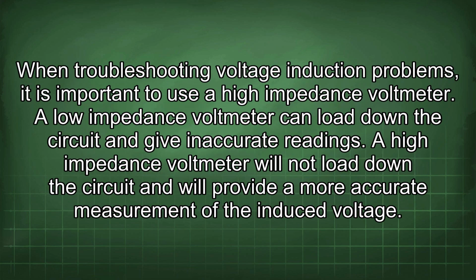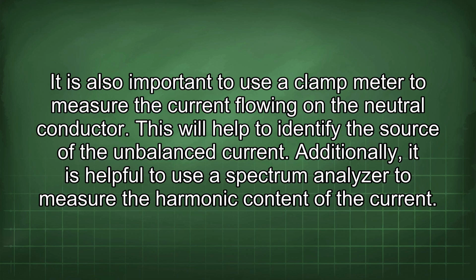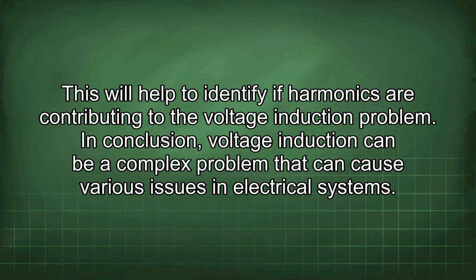When troubleshooting voltage induction problems, it is important to use a high impedance voltmeter. A low impedance voltmeter can load down the circuit and give inaccurate readings. A high impedance voltmeter will not load down the circuit and will provide a more accurate measurement of the induced voltage. It is also important to use a clamp meter to measure the current flowing on the neutral conductor. This will help to identify the source of the unbalanced current. Additionally, it is helpful to use a spectrum analyzer to measure the harmonic content of the current. This will help to identify if harmonics are contributing to the voltage induction problem.